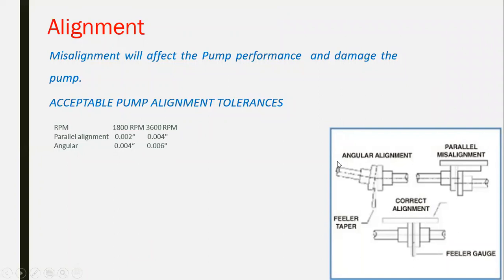And these are enlarged graphs and pictures of how it has to be clearly aligned. So this kind of misalignment, it has to be exactly aligned. The alignment of the pump itself has to be inspected by the manufacturer before the handing over, during the inspection and the final installation. And they do it with a laser to assure the alignment between the shaft of the driven device and the pump itself.